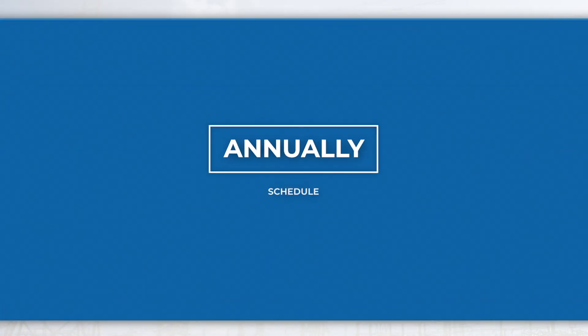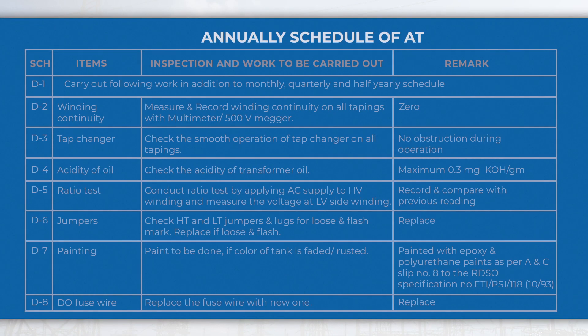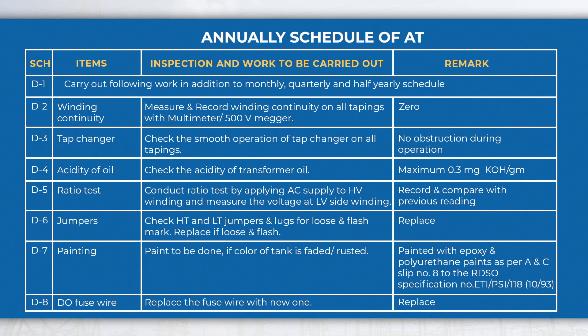In the annually schedule, perform activities like measuring winding continuity, checking the acidity of transformer oil, and conducting ratio test, etc., in addition to half-yearly, quarterly, and monthly schedule activities.